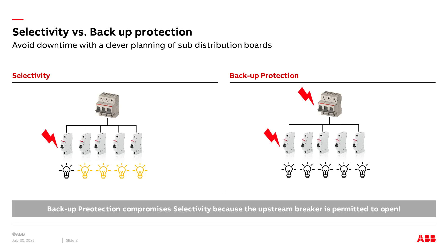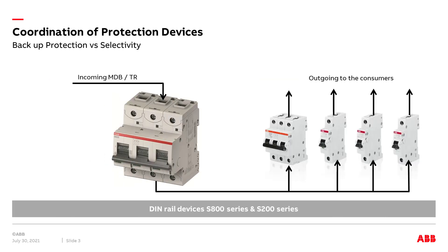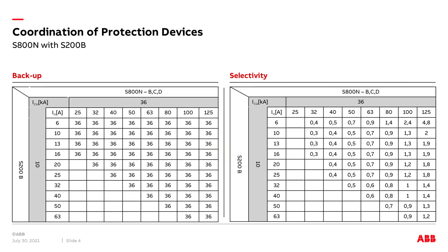Backup protection is very often used in industrial applications. In this first example, an S800 — a high-performance miniature circuit breaker — is used as an upstream breaker. The breaking capacity of this device is 36 kilo amperes. The branches are protected with S200 miniature circuit breakers rated at 6 kilo amperes. The easiest way to find the coordination values is to use the coordination tables in the main catalog.